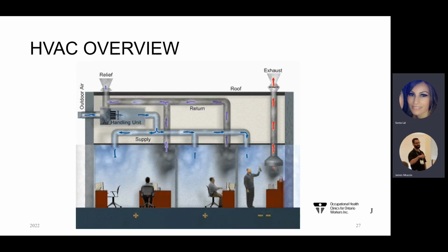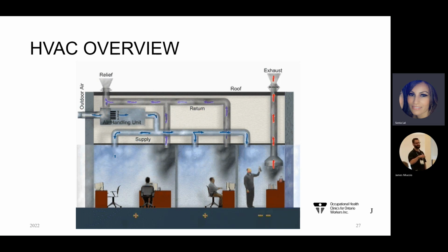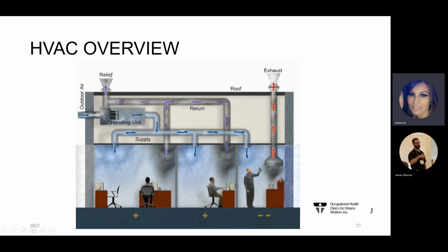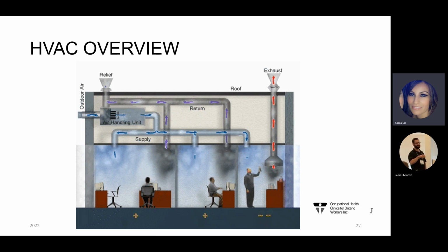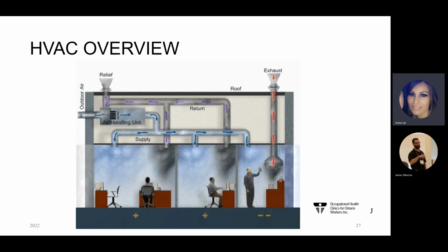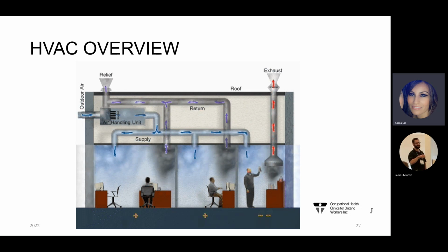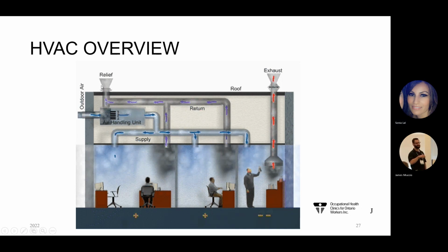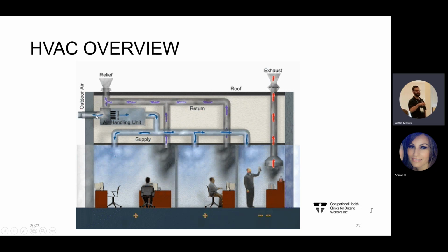Pointing to the outdoor air intake, all the way to the left, notice where the exhaust is, on the rooftop, going perpendicular. That's important to note: generally in office buildings and workspaces, the outdoor air intake and the exhaust systems for various processes should be oriented so they are away from each other. They shouldn't be together, because the outdoor air intake would just pull in the exhaust. The outdoor air and exhaust systems should be several feet apart, if not more, and at different locations of the building, because you don't want exhausted air coming back in.